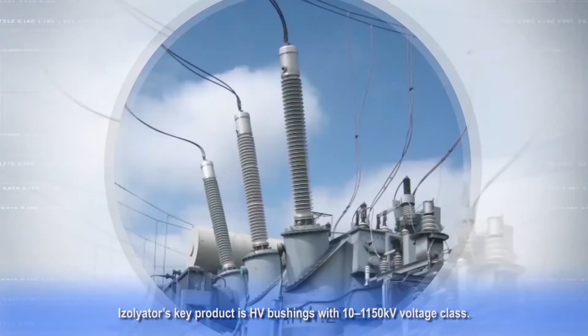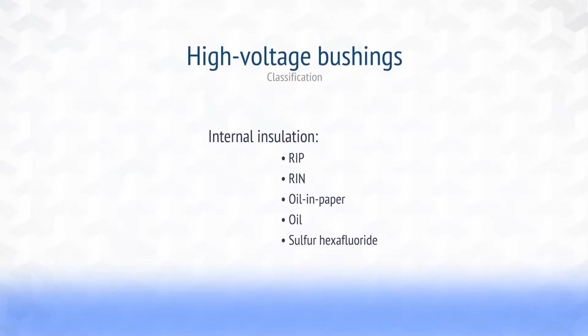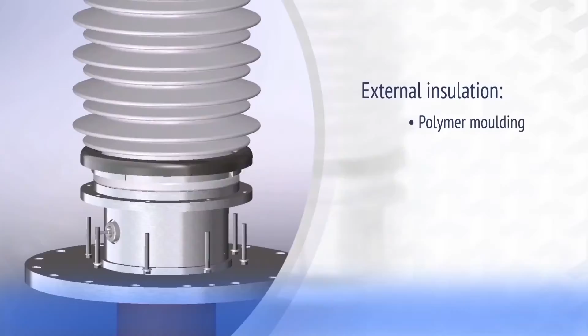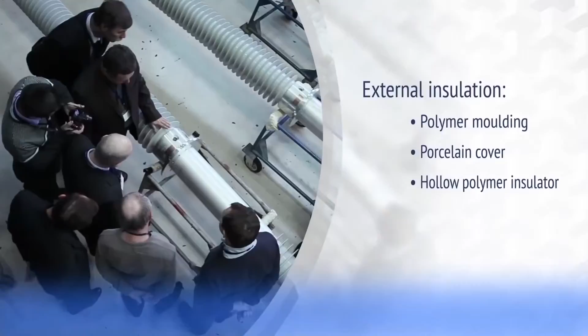The product range includes all basic types of AC and DC bushings operating in working substances: air-to-oil, air-to-air, oil-to-oil, and oil-to-SF6 gas. The enterprise makes RIP, RIN, OIP, oil and SF6 insulated bushings with external insulation executed with either resin casting, ceramic cover, or hollow-type resin insulator.